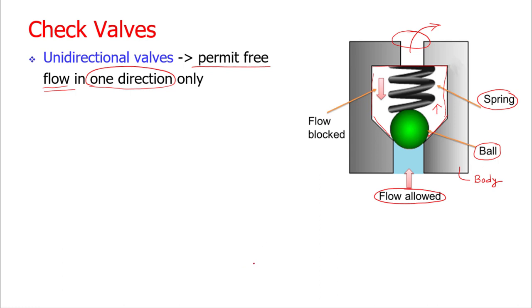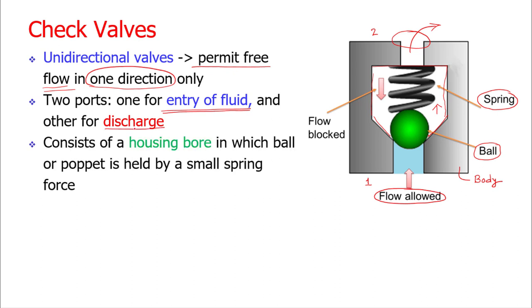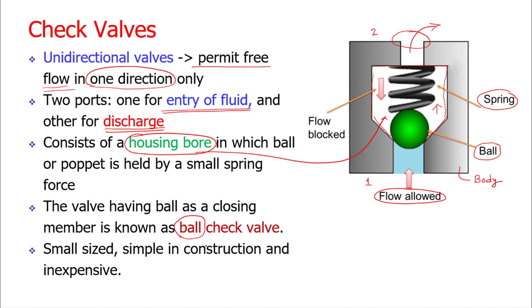There are two ports: one for fluid entry and one for discharge. This is the housing bore in which a ball or poppet is held. If a ball is used to check the fluid flow, it is called a ball check valve; poppet-based valves are also available. These valves are small in size, simple in construction, and inexpensive. For domestic purposes, such valves are used to control water flow. They are generally made of plastic (PVC) or metals such as brass, stainless steel, or bronze.